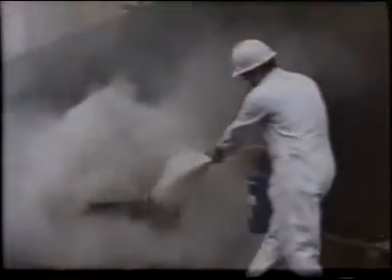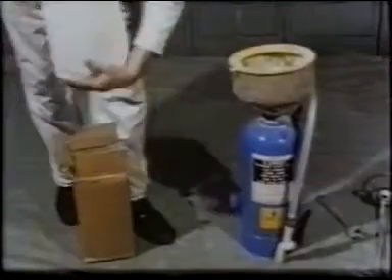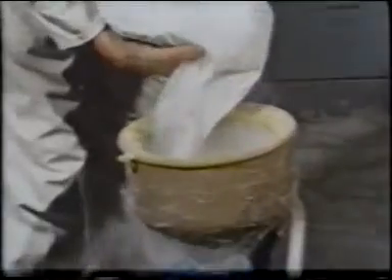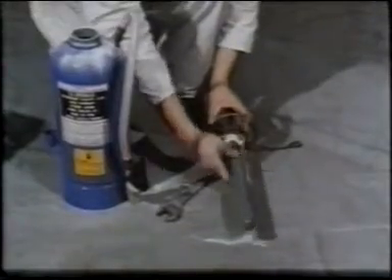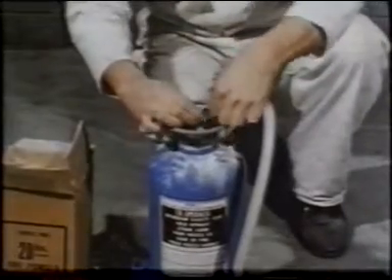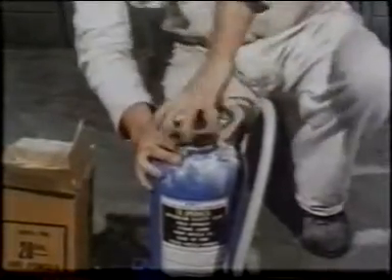They can also be used safely on fires involving live electrical conductors, although they have no cooling effect and lack the penetration of water. Special powders coat carbonaceous material and prevent continued combustion. There are also special powders for metallic fires. The powder extinguishers are relatively easy to refill, with measured amounts of powder and new cylinders of CO2. If only part of the extinguisher is used, it should be recharged. As with any extinguisher, make sure that any remaining CO2 charge has been released before dismantling.